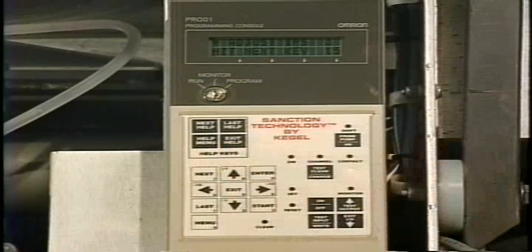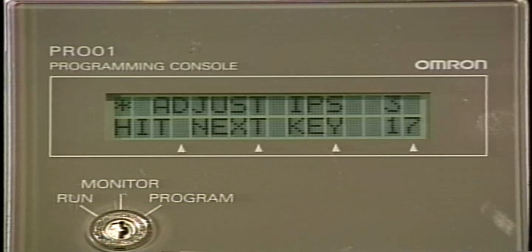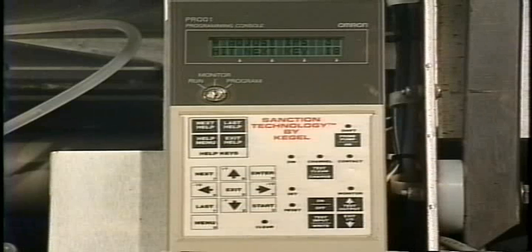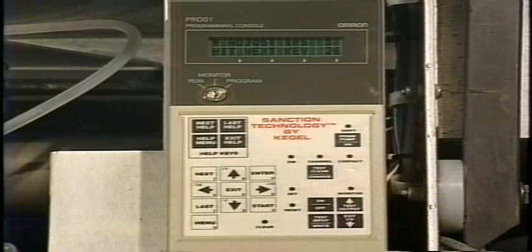Speed 3 will be 17 to 18 inches per second. And notice that the drive speeds all increase by a level of 4 inches per second until we hit our final speed, which will be high speed. Speed 4 will be 21 to 22. Speed 5 will be 25 to 26. Speed 6 will be 29 to 30. And speed 7, which is your final speed, will be high speed.